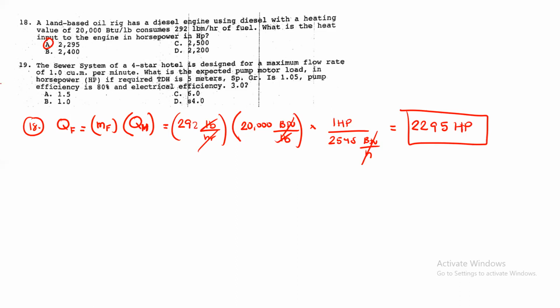The next, number 19. The sewer system in a 4-star hotel is designed for a maximum flow rate of 1 cubic meter per minute. So what is the expected pump motor load in horsepower if required TDH is 5 meters? So specific gravity daw is 1.05, pump efficiency 80%, and electrical efficiency is 3.0. So paano tong 19 guys? So simpleng gamma QH lang yan.